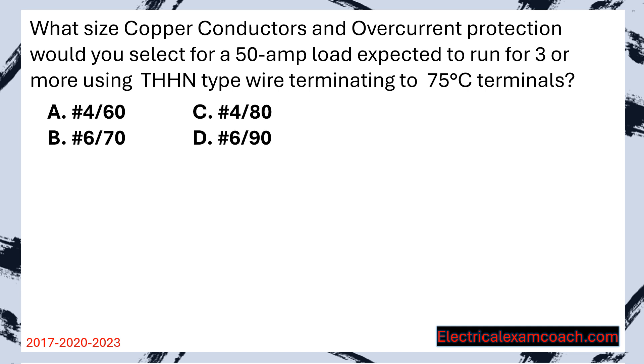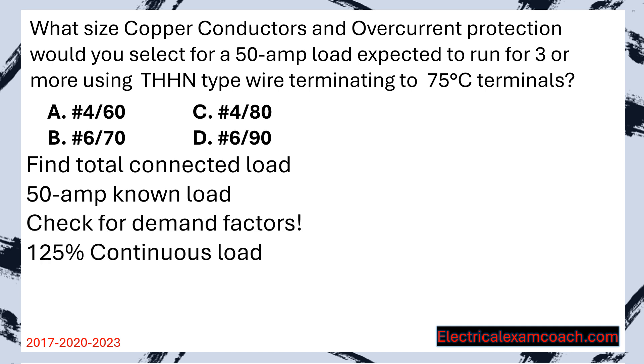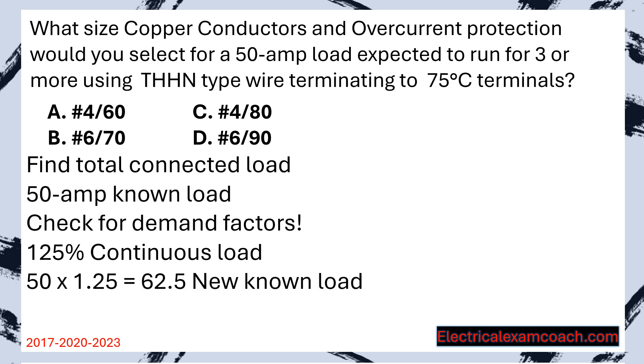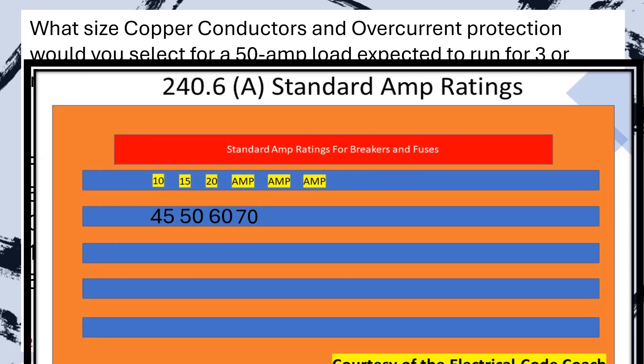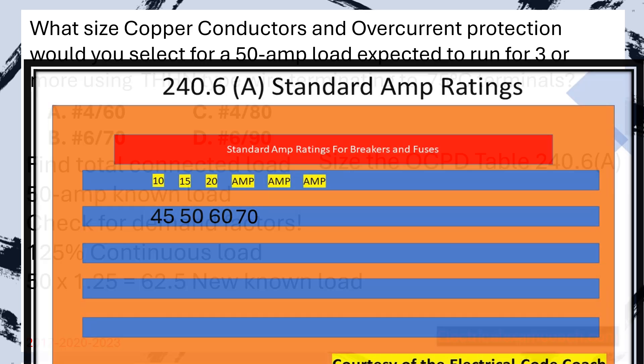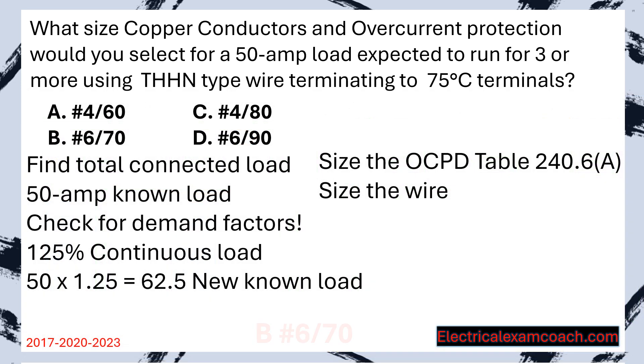What size copper conductors and overcurrent protection would you select for a 50 amp load expected to run for three or more hours using THHN type wire terminating to 75 degrees C terminals? Step one: find the total connected load — starting known load is 50 amps, but we must check for demand factors. It's a continuous load so we apply the 125% rule: multiply by 1.25, giving us a new known load of 62.5 amps. We head to our table and choose the next standard size, which is a 70. Heading to our primary ampacity table on the copper side in the 75 degrees C column, we find a wire that meets or exceeds the known load — a 6 gauge wire on a 70 amp breaker.